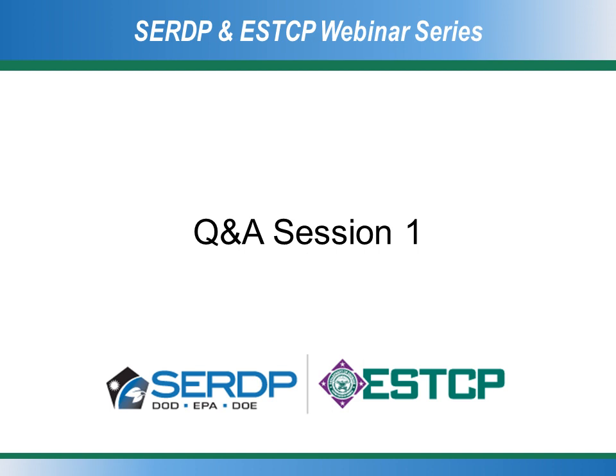Yes, good point. Part of this demonstration was actually working with occupants at Tinker on this demonstration building site to effectively get more data to understand what was a good level to maximize savings but still not cause complaints. And this is a little bit self-regulated with performance contracts many times, because these ESCOs are responsible for the ongoing maintenance and handling support calls. The more calls they get from people that are uncomfortable, they end up paying for it on the maintenance side of things. So that was another key result from this, really dialing in and understanding what a reasonable level of night setback and comfort ranges during occupied timing is to maximize savings.